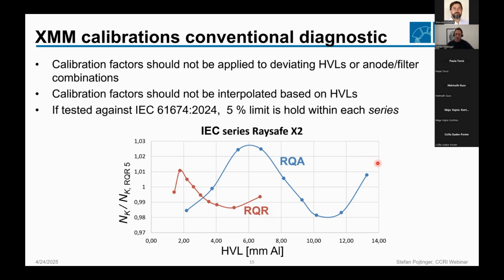And also, we recommend to not use a calibration factor that has been determined for a specific combination or a specific series for another one. For example, here you can see between RQR and RQA, you have a difference of several percent if you want to use one calibration factor from one series for the other.